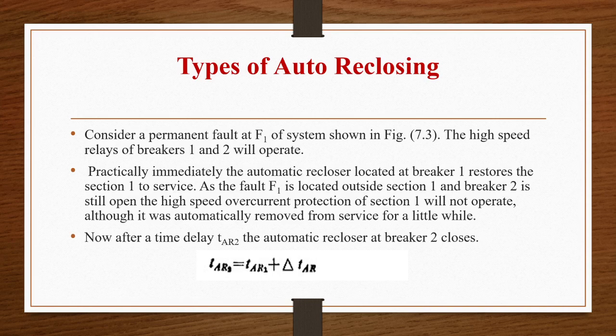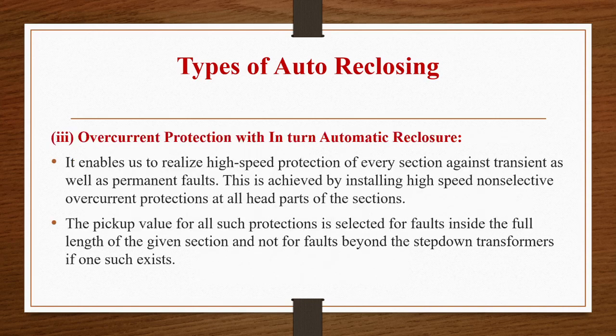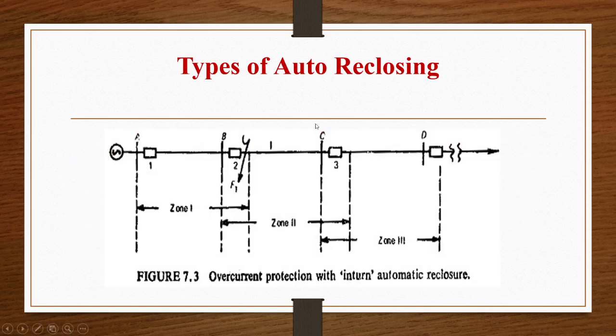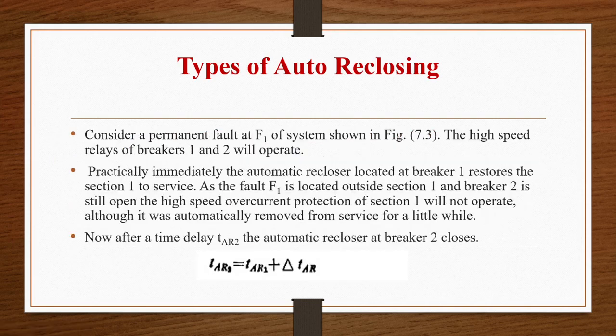So what is happening? There is an occurrence of a permanent fault F1 in the system as shown in the figure. Here we can see the permanent fault F1 which is occurring, and high speed relays of circuit breakers 1 and 2 will operate, and practically immediately the automatic reclosure which is located at breaker 1 will restore section 1 to service.